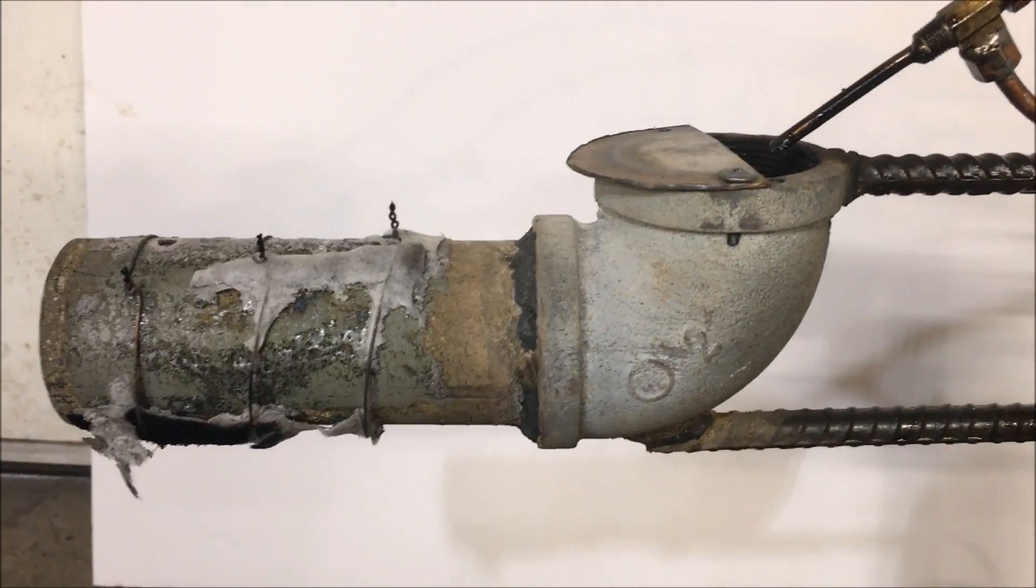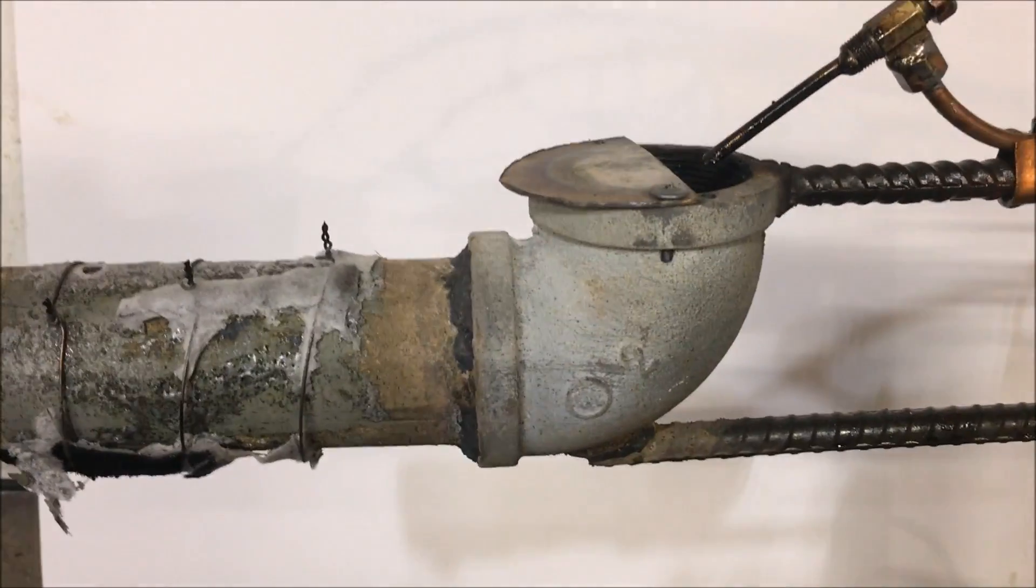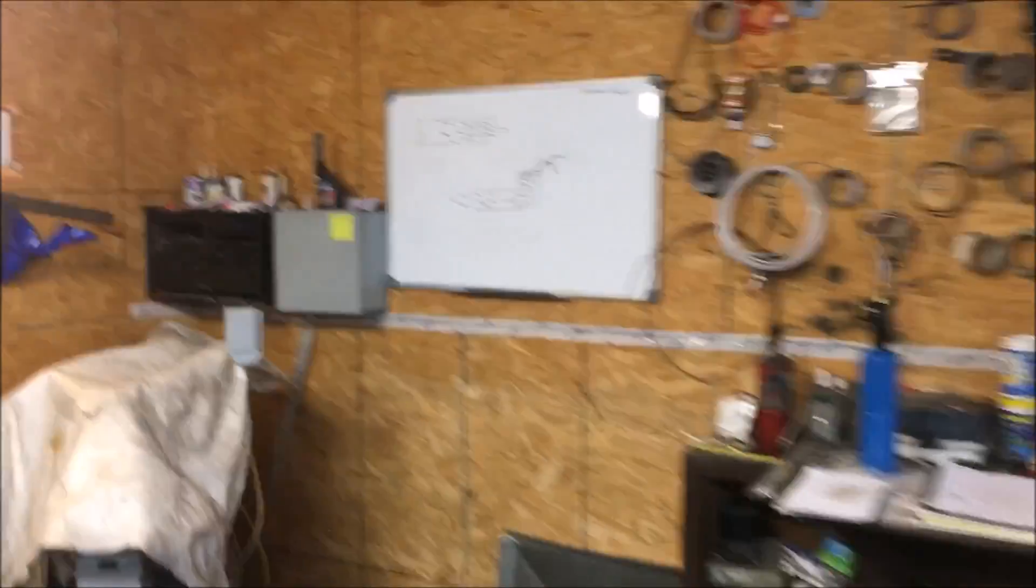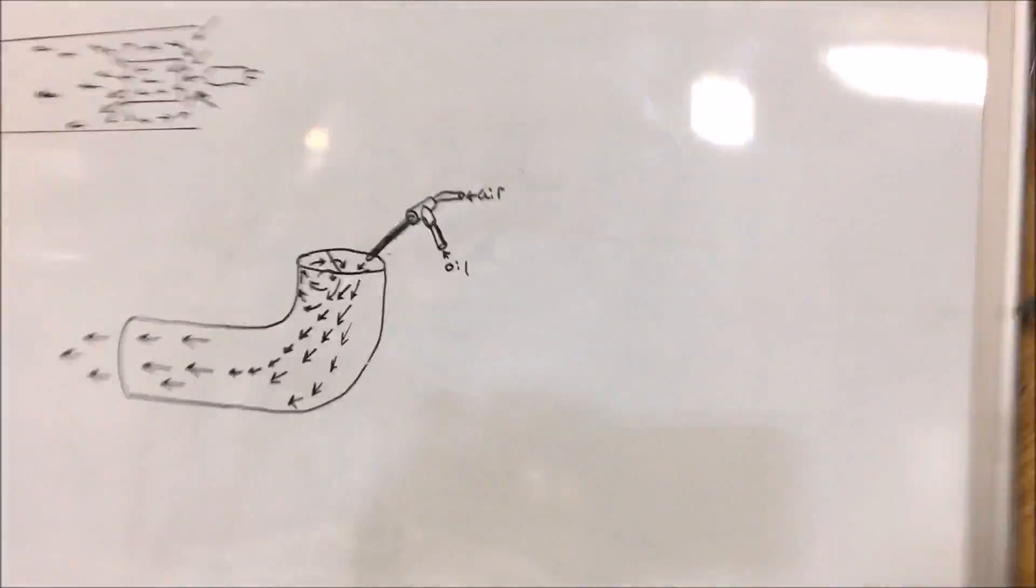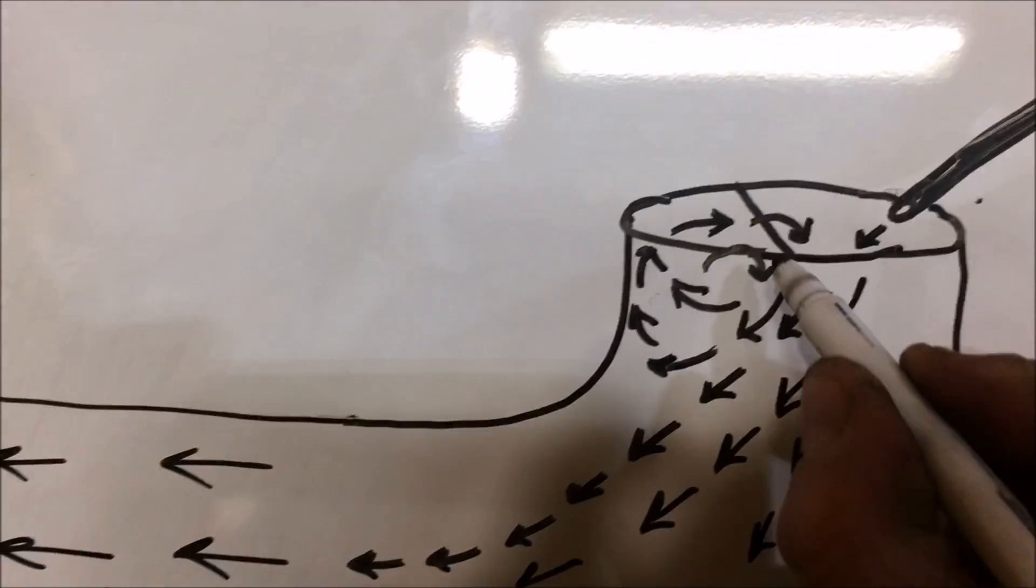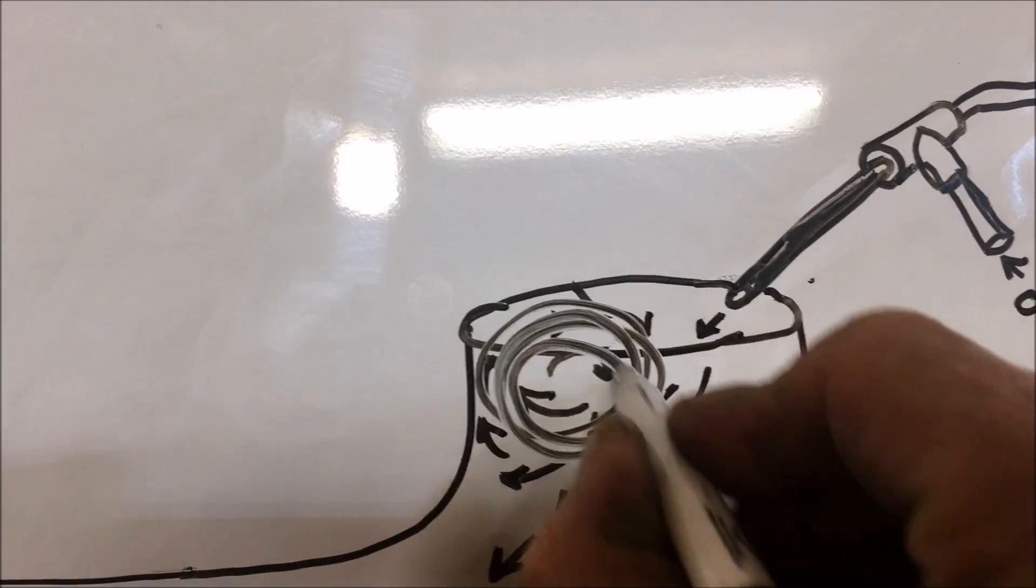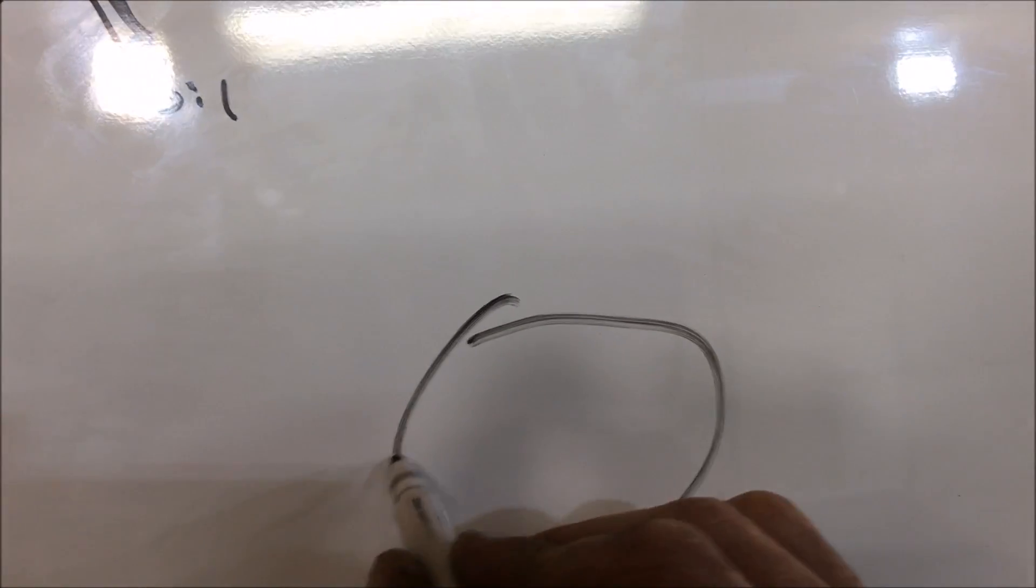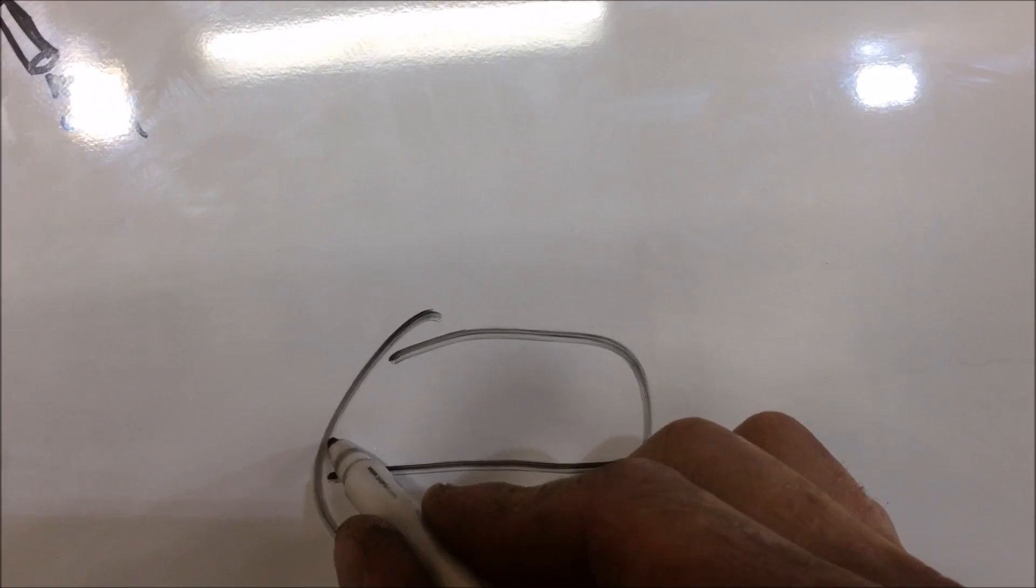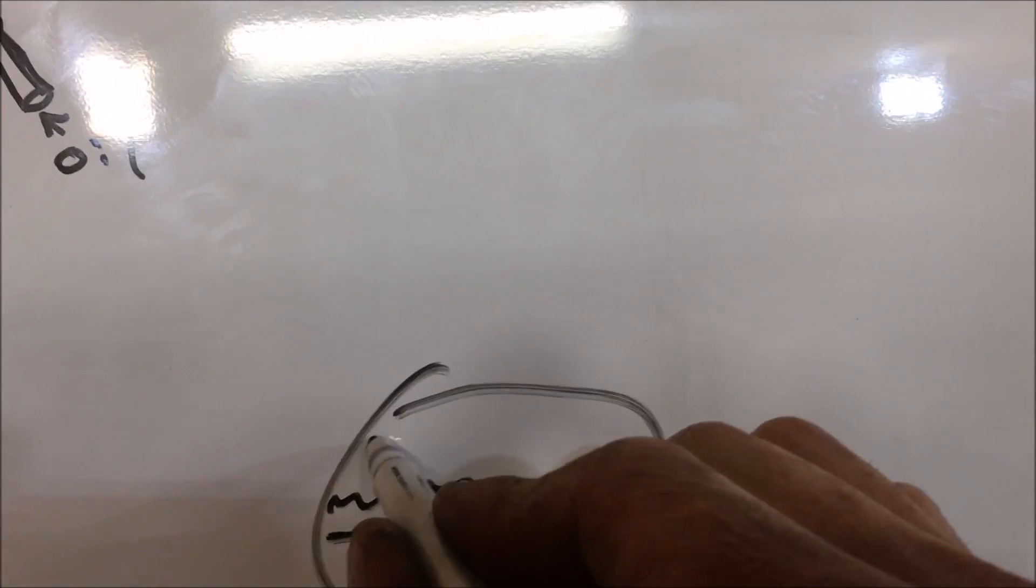Because this elbow causes a recirculation event at the throat, it enables a very stable flame. It's continuously reigniting gases or vaporized oil. I'm going to show you a little illustration here of what we have. Basically this is what is happening: you will see a little rolling ball of fire like this, and it's cylindrical and it goes about the throat of the burner.